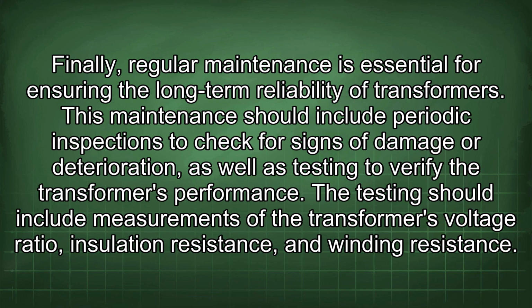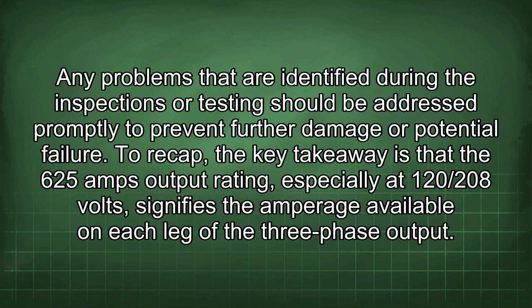Finally, regular maintenance is essential for ensuring the long-term reliability of transformers. This maintenance should include periodic inspections to check for signs of damage or deterioration, as well as testing to verify the transformer's performance. The testing should include measurements of the transformer's voltage ratio, insulation resistance, and winding resistance. Any problems that are identified during the inspections or testing should be addressed promptly to prevent further damage or potential failure.